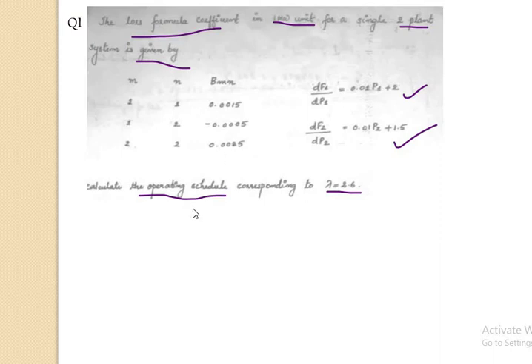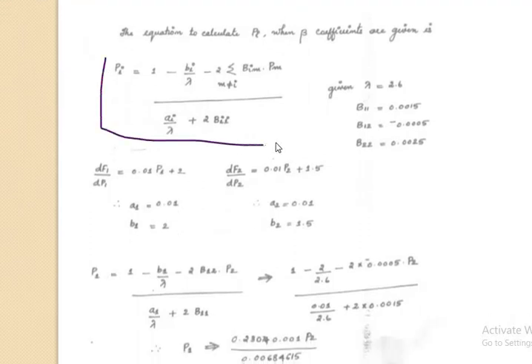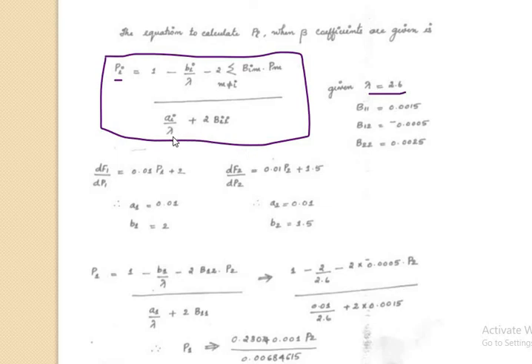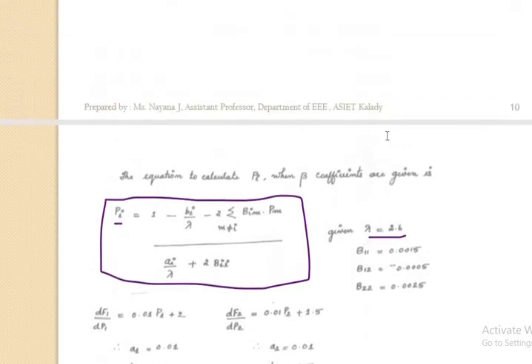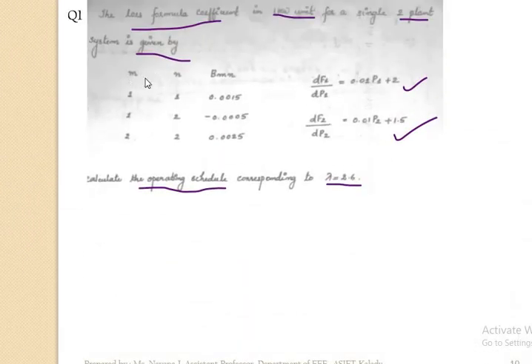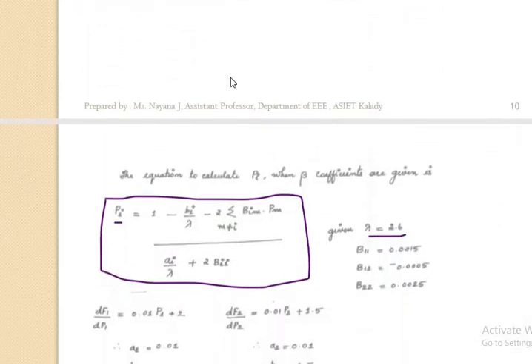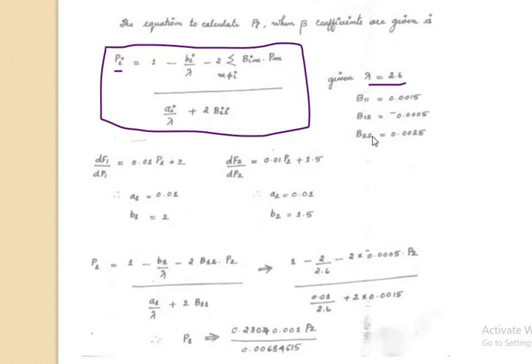How do we calculate P1? We have one equation for that — the equation for calculating generated power Pi. Lambda is given as 2.6. Also given are M, N, and B_MN values. When M=1, N=1, that term is B11; when M=1, N=2, it is B12; when M=2, N=2, it is B22. So B11, B12, B22 are all given. Additionally, dF1/dP1 and dF2/dP2 are given.